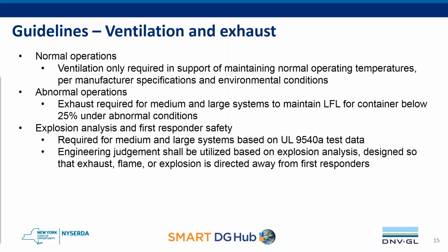The ventilation and exhaust requirements under normal operations, and because this is specific to lithium ion and for outdoor systems, we understand that gases are not output by lithium ion systems under normal operating conditions. So ventilation is only required to support thermal management of the system. So that's per manufacturer specifications, and if the thermal management is handled in a different way, then it wouldn't necessarily be required.